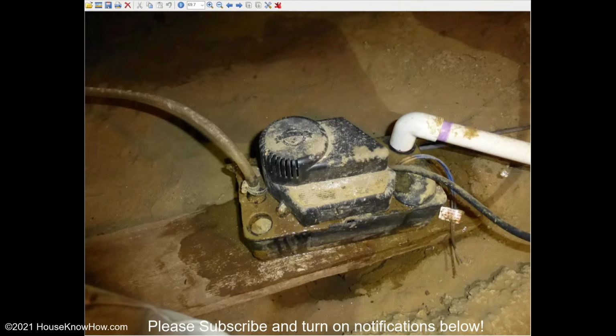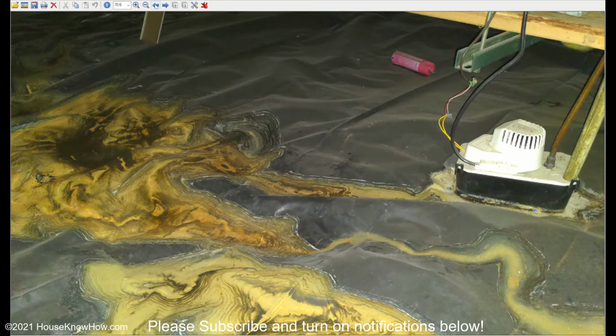Here we go. This one is not wired in and it's failed. It's overflowing. Water is overflowing the pump and dripping onto the surrounding area. Now, these pictures show condensate pumps in crawl spaces, but they're often installed on floors in living spaces like the one I showed at the start of this video.